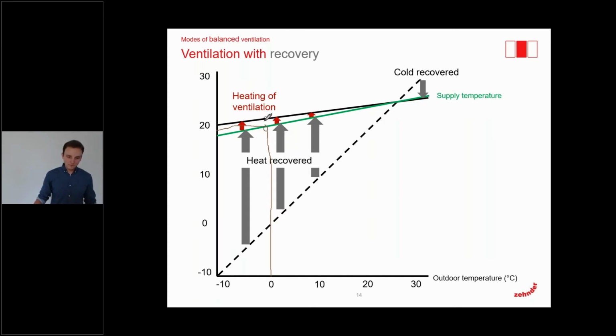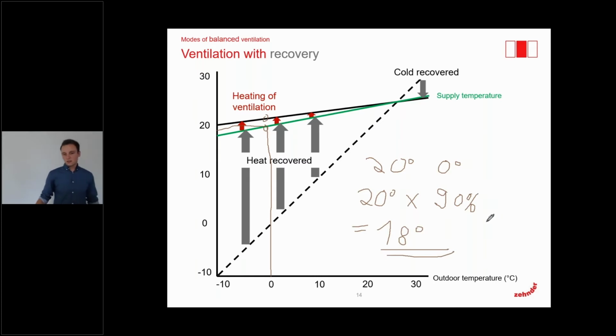So let's make it easy. We want to have an inside temperature of 20 degrees and we have an outside temperature of 0 degrees. So we have a temperature difference of 20 degrees. And now we have a heat recovery with an efficiency of 90%. So what we get is a supply air temperature of 18 degrees. Now the temperature gap is quite small. We just need to heat up the air about 2 degrees. And the same also applies in summer when we are using the cold recovery.